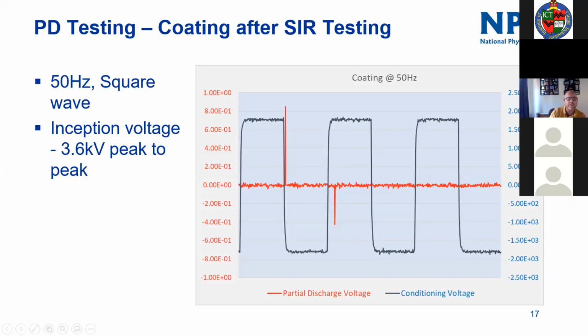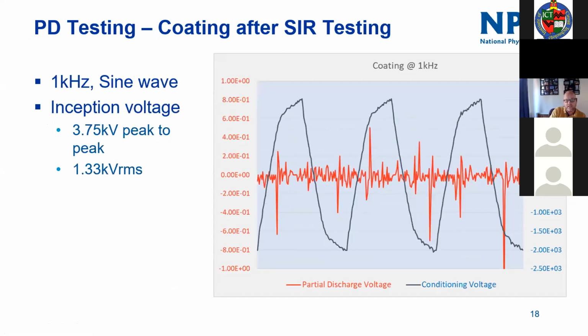If you start to put a square waveform across it, in this case just at 50 hertz, you can see partial discharge occurring periodically through the system. That's got an inception voltage with this square waveform of about 3.6 kilovolts peak to peak. This shows a 1 kilohertz sinusoidal wave across the same sample, and its inception voltage to start the PD. You can see the PD is a lot more noisy here. It's beginning to occur at different parts of the cycle as well, basically because our amplifier is struggling to drive nearly 4 kilovolts at 1 kilohertz, and we're in the process of upgrading that, hopefully. But anyway, that's talking about 1.3 kilovolt RMS. So that's not far above the 1,000 volt DC systems that we've been playing with for a couple of years. And you can see lots of partial discharge occurring with this higher frequency system.